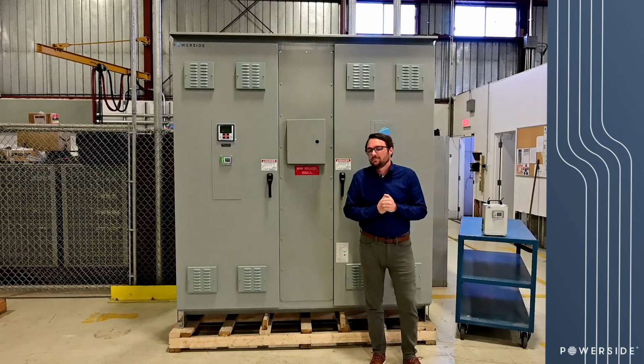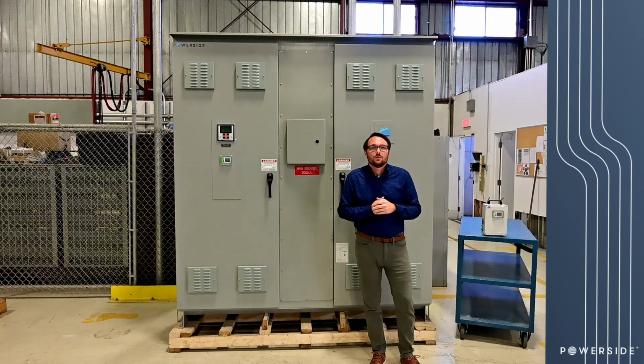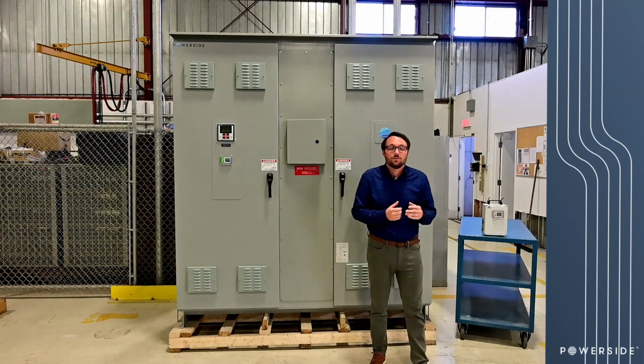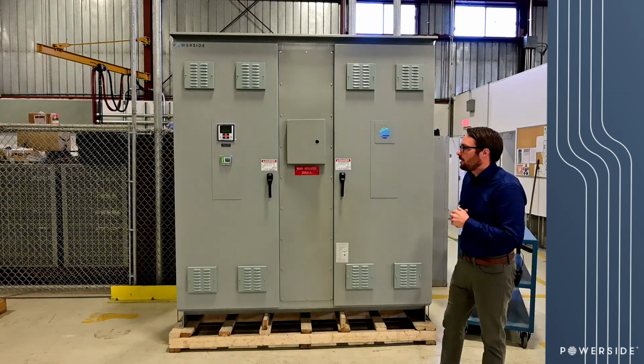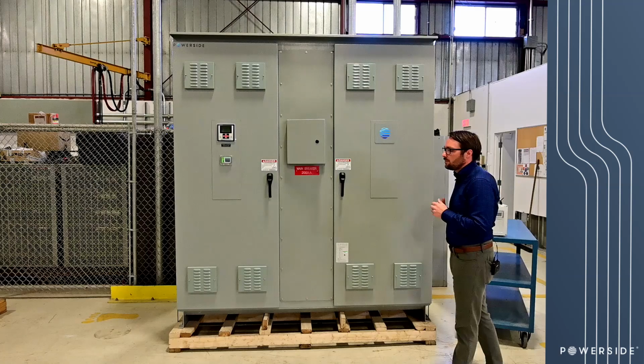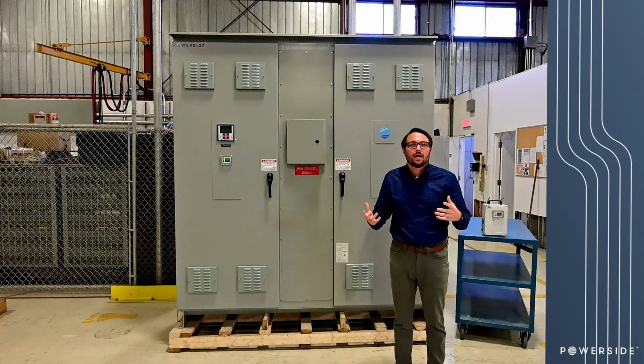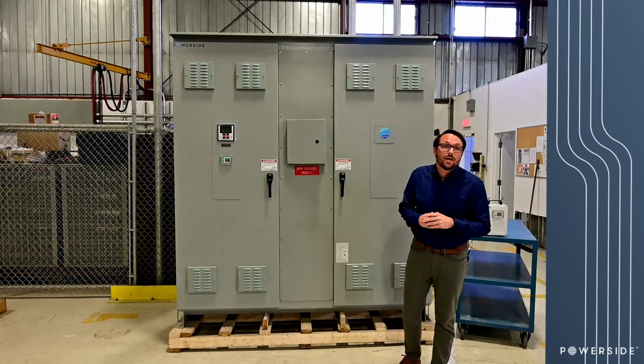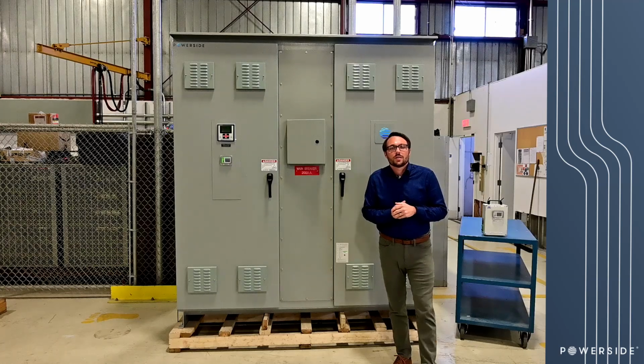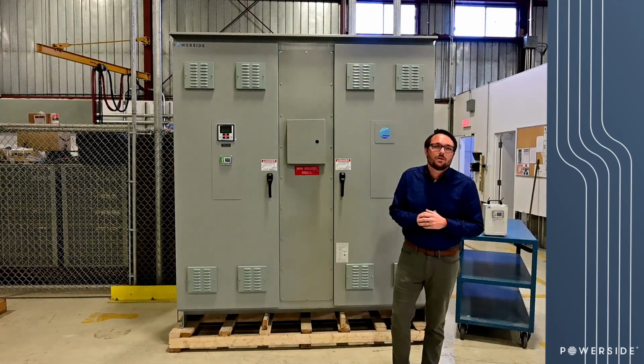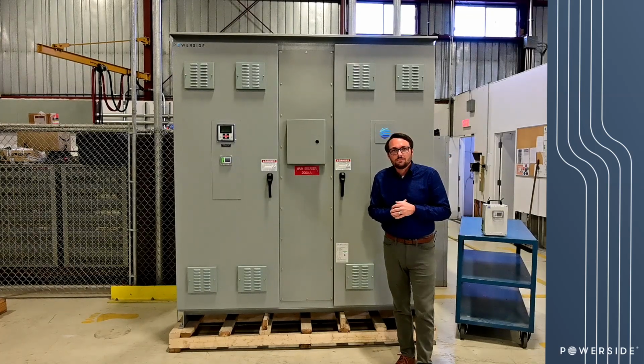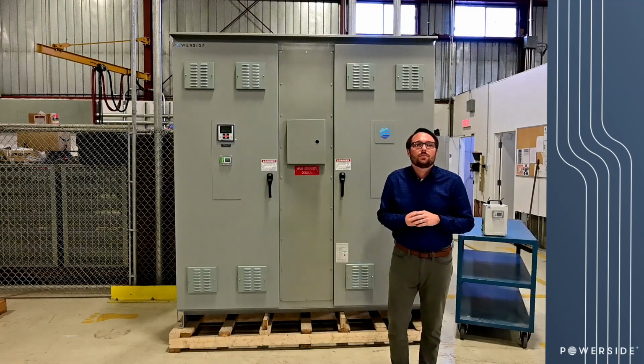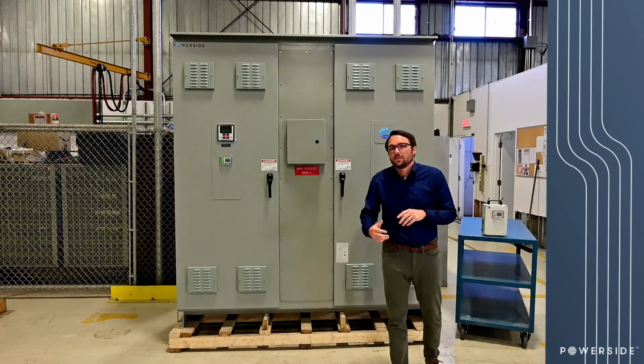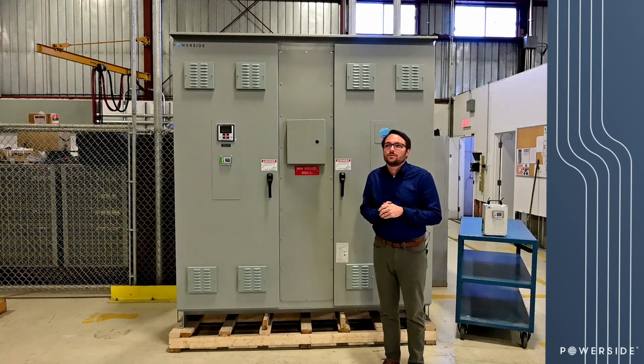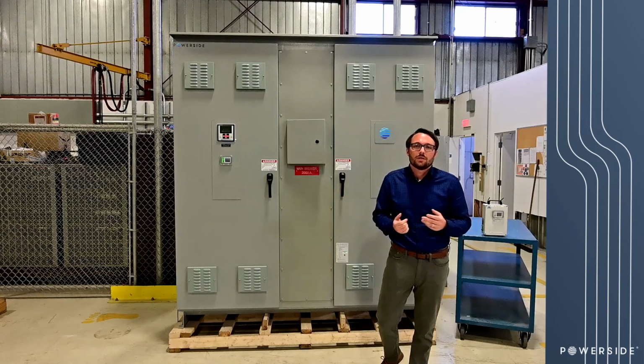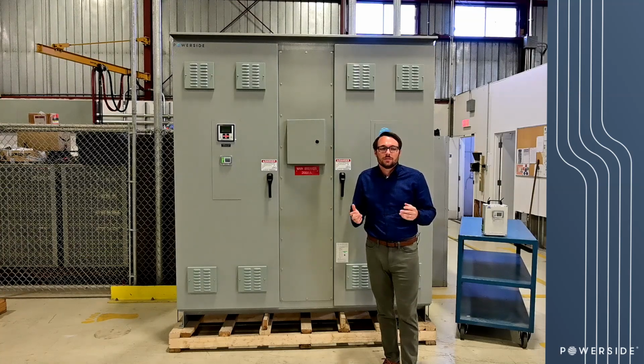This facility runs typically 2 to 3 shifts a day, so their load is quite significant and changing quite frequently. This client came to us for a power factor related penalty that they were receiving from their utility power provider. Now, it's very common in North America and really across the world to have a power factor requirement that consumers have to abide by, and if they don't, they get charged extra on their utility bill. This particular client was paying anywhere between $18,000 and $20,000 per month in power factor penalties. And so certainly that caught the eye of their senior management to try to figure out what can we do to cut down the cost of these penalties.